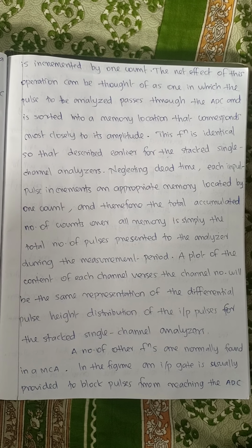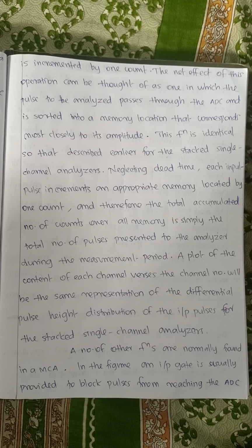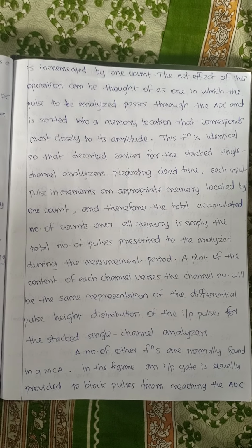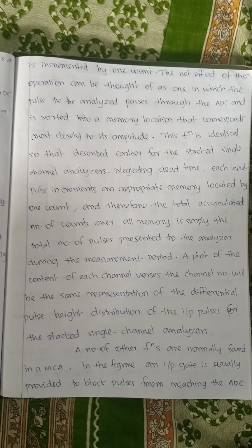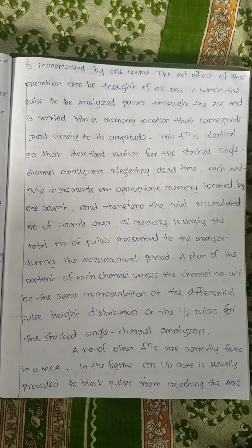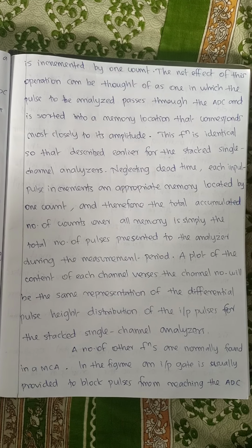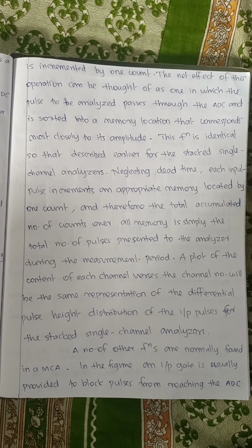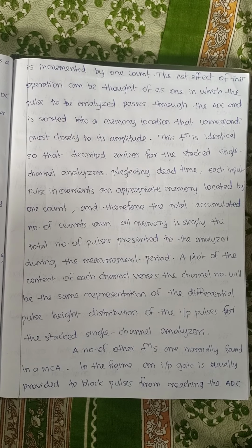The net effect of this operation can be thought of as one in which the pulse to be analyzed passes through the ADC and is sorted into the memory location that corresponds most closely to its amplitude. This function is identical to that described earlier for the stacked single-channel analyzers.